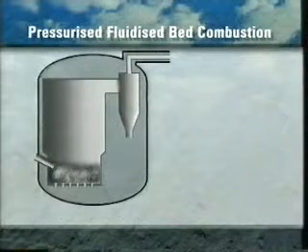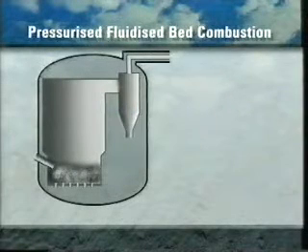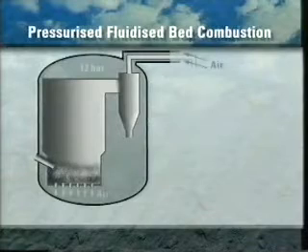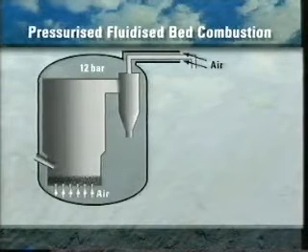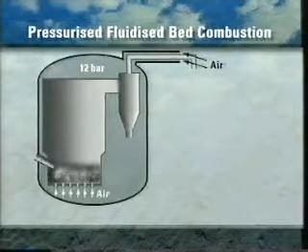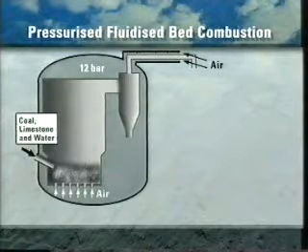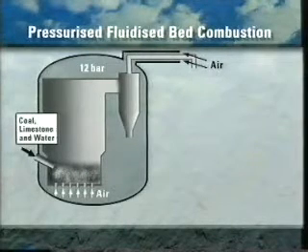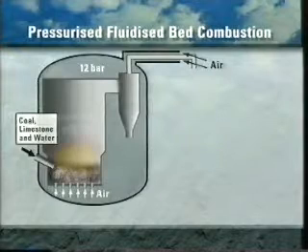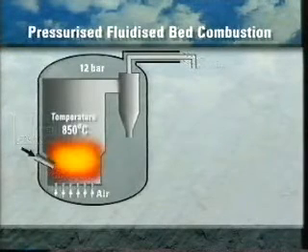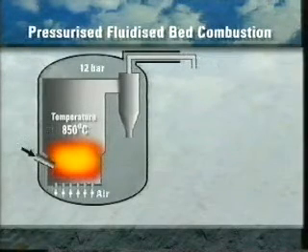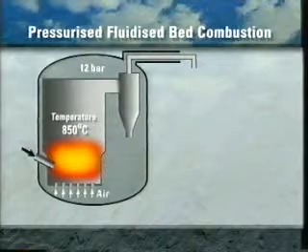In a pressurized fluidized bed combustor, PFBC, combustion air at a pressure of 12 to 16 bar is delivered to the bed. Crushed coal and limestone, sometimes mixed with water to form a pumpable paste, is fed into the fluidized bed.